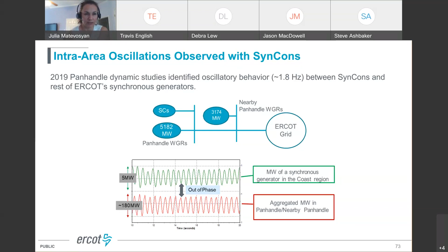But what also happened in 2019 Panhandle dynamic studies, we identified oscillatory behavior between the synchronous condenser and the rest of the synchronous generation in the central and eastern part of Texas. What you can see here is inter-area power oscillations where the synchronous condenser is the main participant. And so we're looking into this. There is a way to control this through reduction of power output from the Panhandle area, but one of the improvements that can be provided is if inverter-based resources in the area provide power oscillation damping, and that's something we're also looking into.